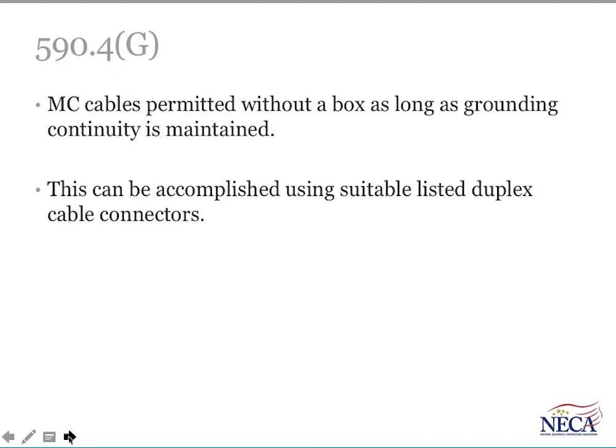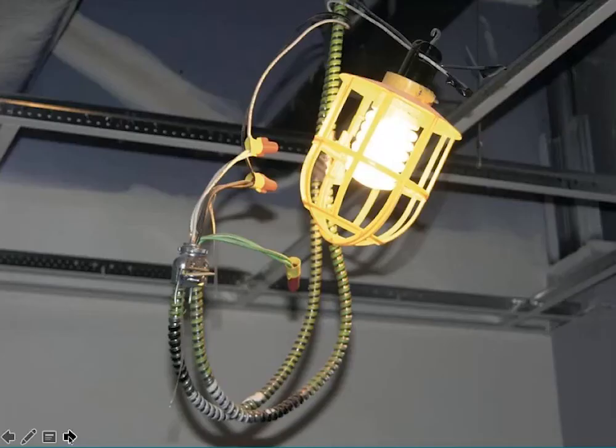Another change in 590.4, Subdivision G, recognizes that MC cables are permitted to be used as a wiring method, and you don't have to install a box for any splice points, as long as grounding continuity is maintained from one length of MC cable to another length of MC cable. And this is often accomplished by using a suitable listed MC cable connector.